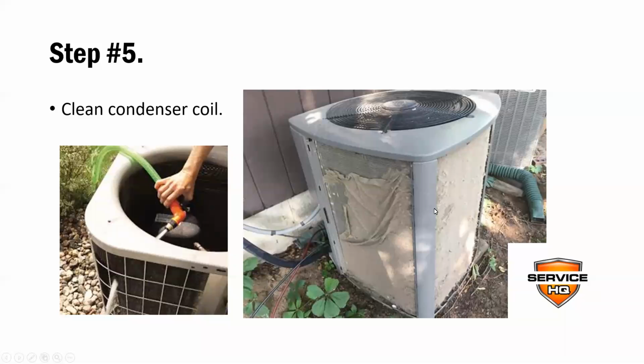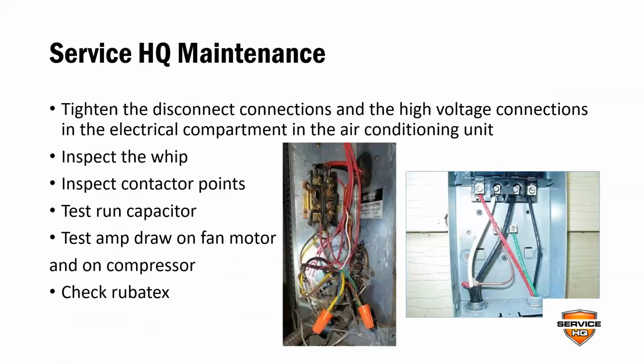So anytime you're mowing, turn your mower around and blow that stuff away from your air conditioner, so it doesn't create an issue. But you can't stop this cottonwood from getting in here. That's why these things need to be cleaned. This is like a clogged artery here. Like, this thing cannot breathe, and if it can't breathe, it's working harder than it needs to. So we take it apart, clean the condenser coil.